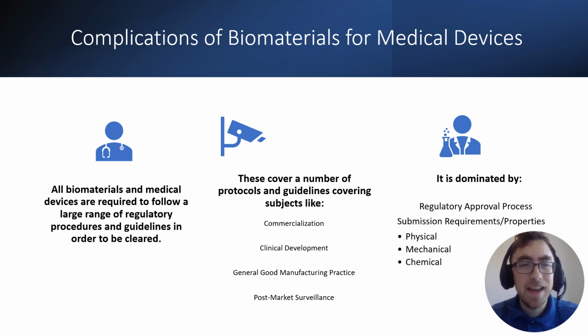Although the FDA acknowledges that many of the currently available biomaterials offer a great deal of potential for use in the creation of medical devices, their qualities and safety must be carefully considered in light of the particular application at hand and the extent of the patient contact. The idea that a material that was deemed safe for one intended use in a device might not be safe in a device intended for another is a key one in the safety assessment of medical devices.